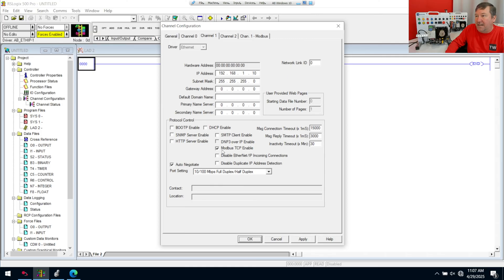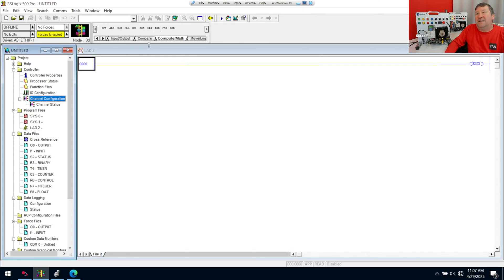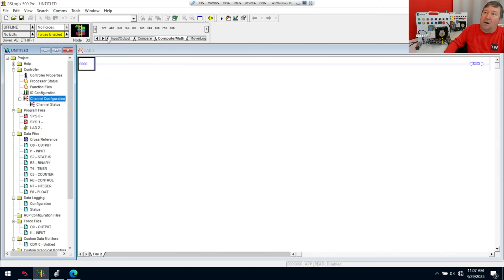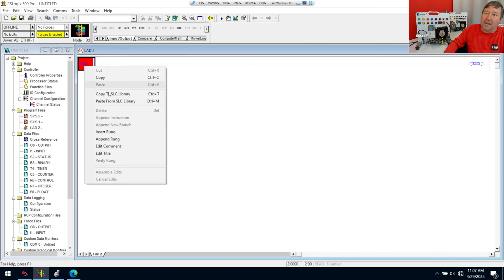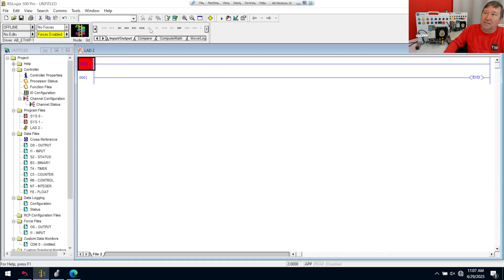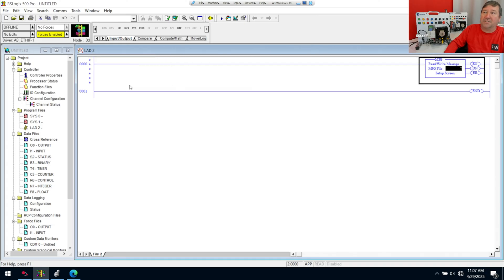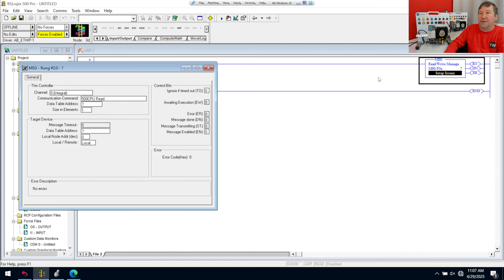And we'll click OK to that. Make sure you got that box right there. Check for the Modbus. Otherwise, you won't have the next option. We are going to go to our input-output category and bring down an MSG instruction. So go ahead and right-click, insert a rung, bring down the MSG instruction.